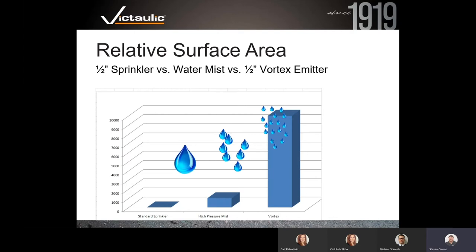The relative surface areas are very important. A sprinkler droplet is about 1,000 microns; a high-pressure mist droplet is about 100 microns; and Vortex droplets are only 10 microns, but there are tens of thousands more of them. The analogy: fill a five-gallon bucket with a basketball versus golf balls to the same level — the golf balls have much greater cumulative surface area. More droplets, smaller droplets, greater surface area — thus more efficient cooling and extinguishment.